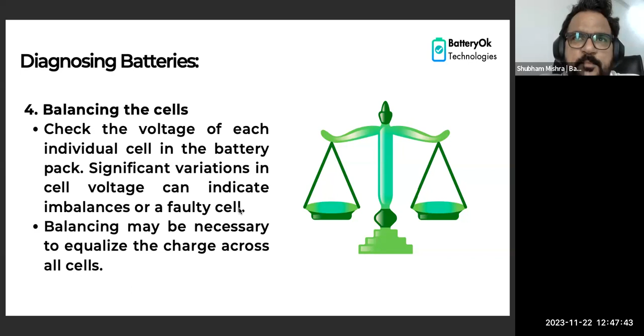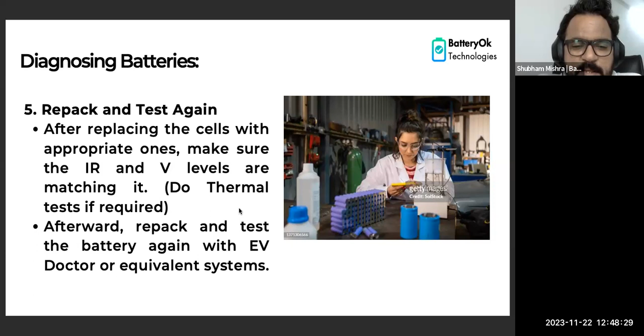Once the test is done, make sure the overall IR or voltage matches the original. Do a thermal test if required, because in many cases, even if the packing is done and it's put inside the enclosure, one of the cells might not behave well due to chemistry issues. Then you need a thermal camera or something that checks the temperature of all the cells along the BMS side. You can use EV Doctor or equivalent systems to get the test done again once the battery is ready.